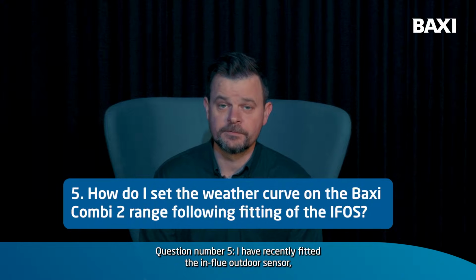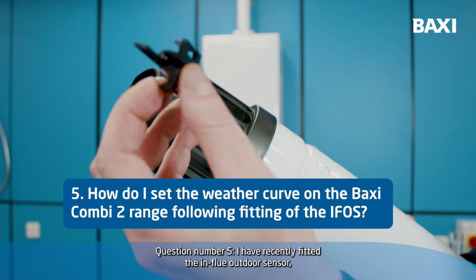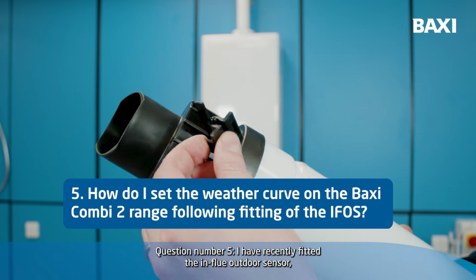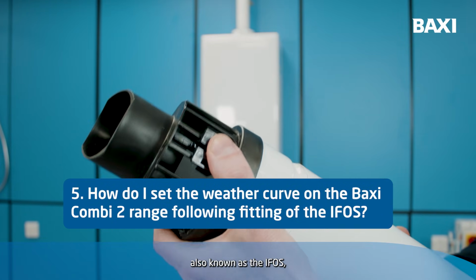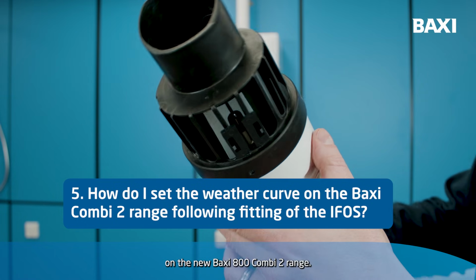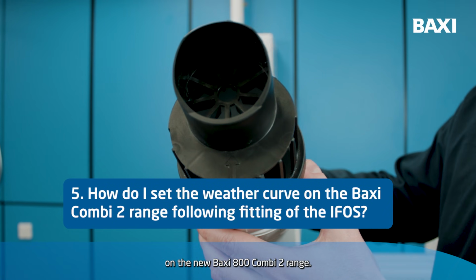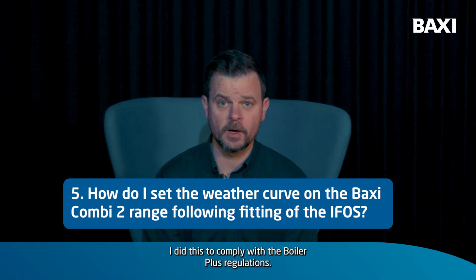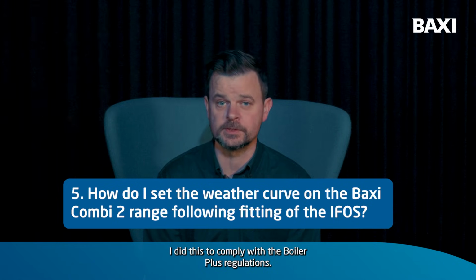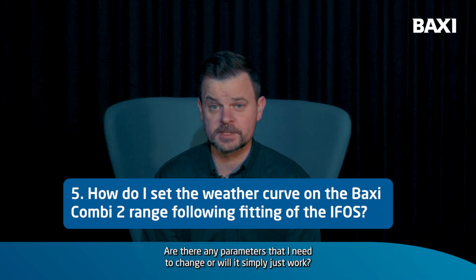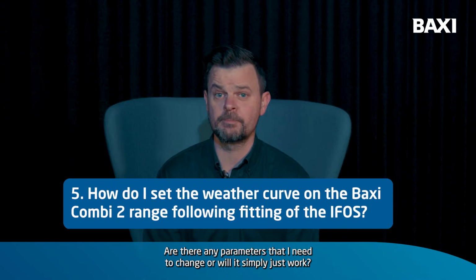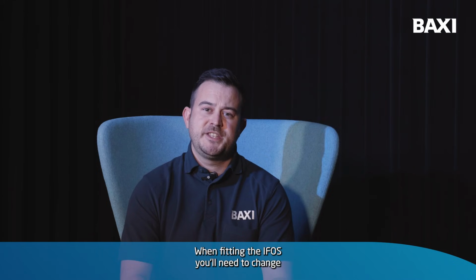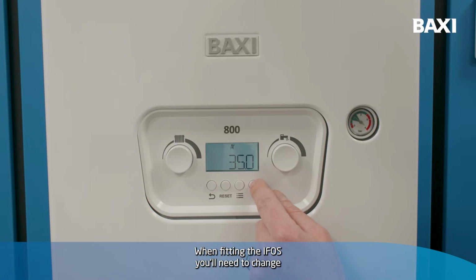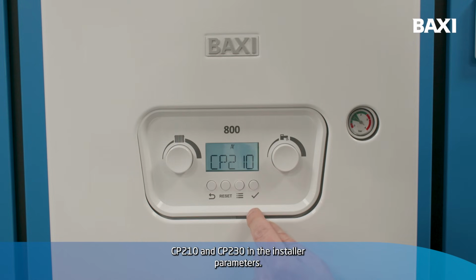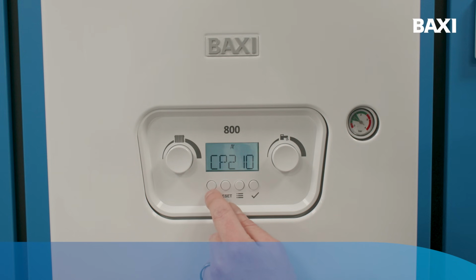Question number 5. I have recently fitted the in-flue outdoor sensor, also known as the IFOS, on the new Baxi 800 Combi 2 range. I did this to comply with the Boiler Plus regulations. Are there any parameters that I need to change, or will it simply just work? When fitting the IFOS, you'll need to change CP210 and CP230 in the installer parameters.